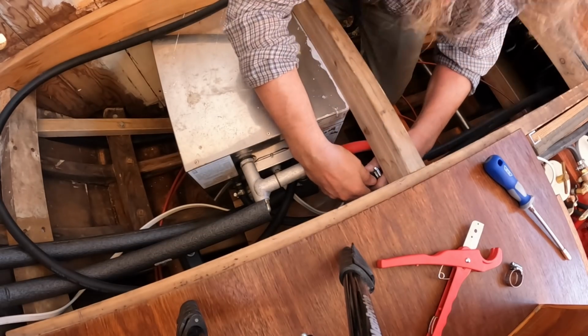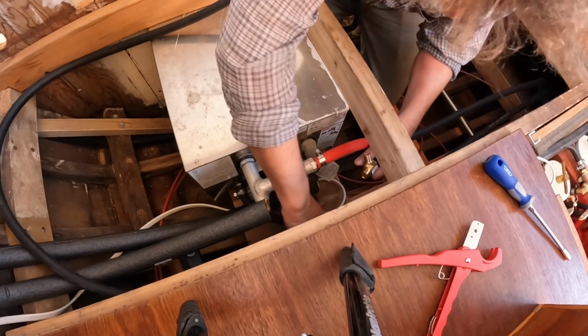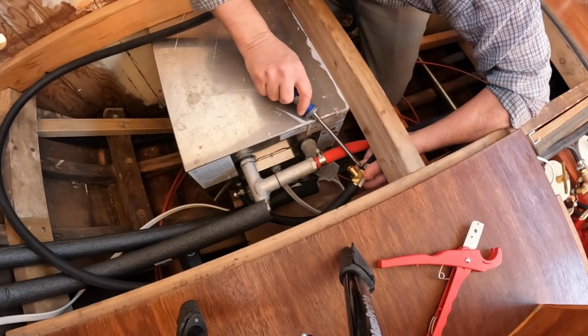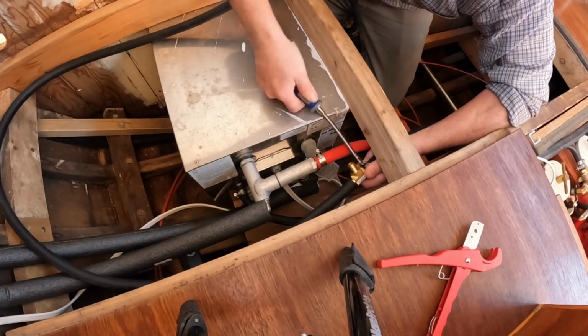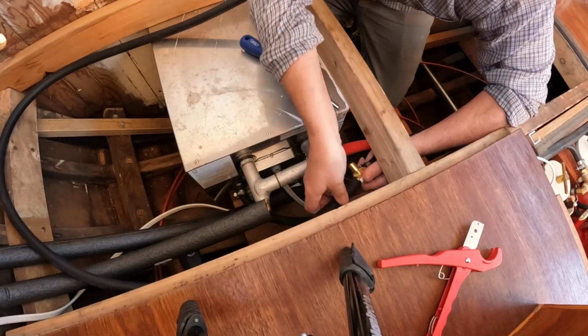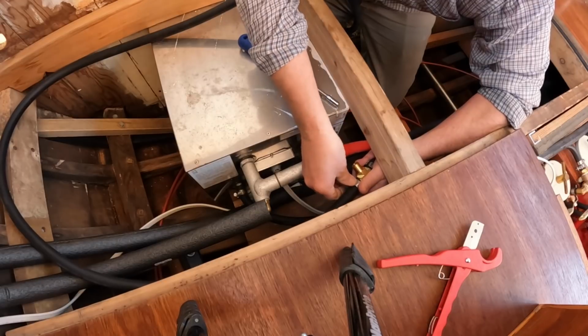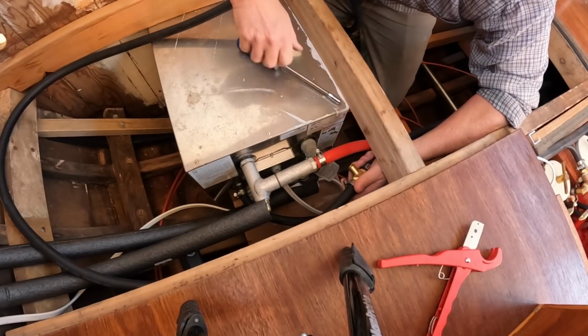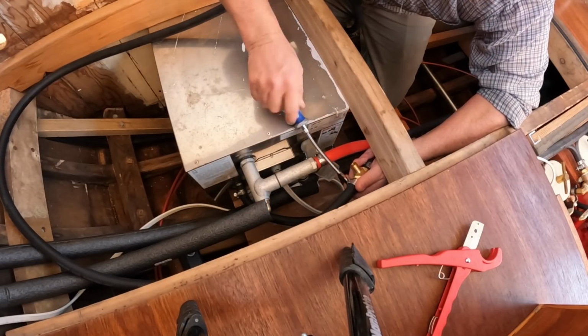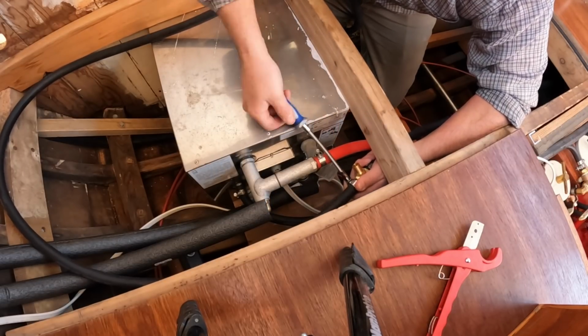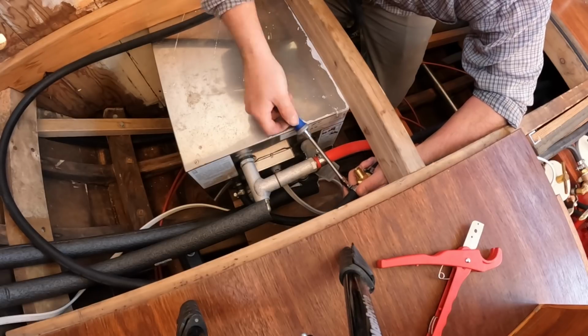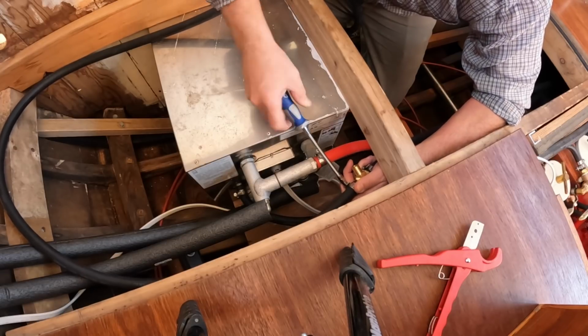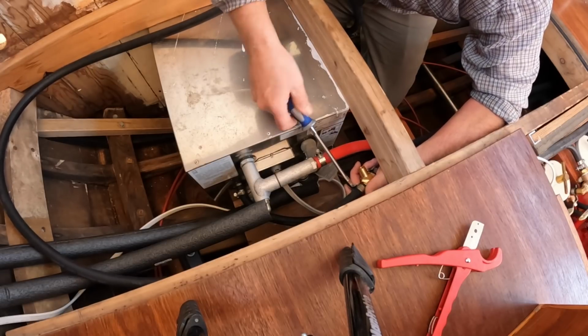T. The other side, that's going to be the vent. Now this is effectively a poor man's air trap, and you'll notice that the water is going to flow through the T and make a 90-degree turn. What that'll do is encourage bubbles to move on and up towards the vent. It would be better if this was vertical, but this is going to be just fine.